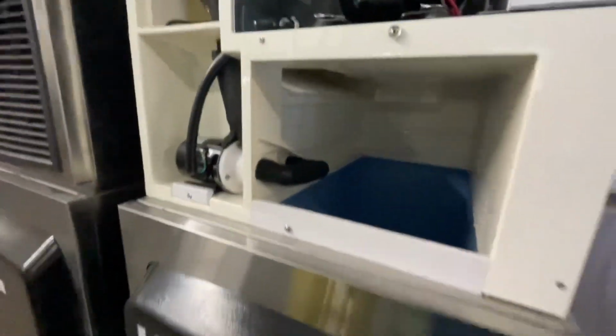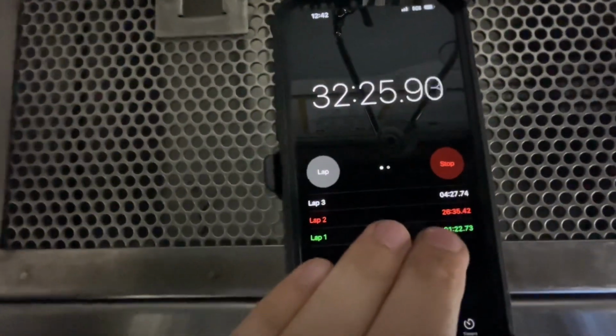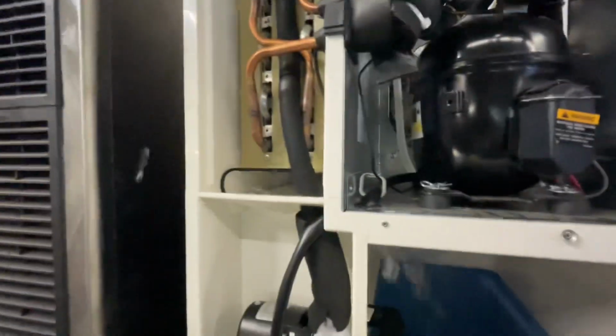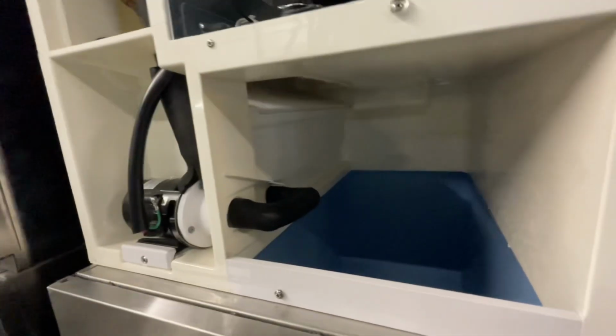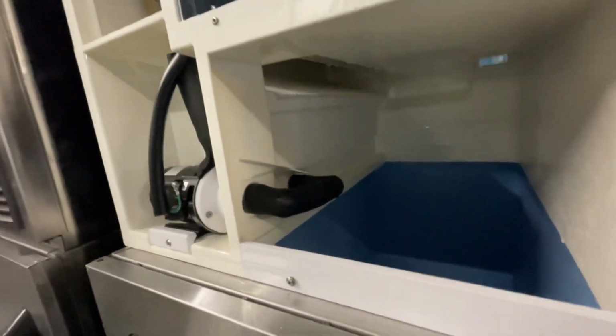So over 4 minutes into our harvest, let's see if we can get a good shot of what's going on over there. You still see ice cubes all over that evaporator. They should be mostly gone by this point. That's a 26-minute freeze, 4.5 minutes into harvest. Still have, there's a good shot, but more than likely it experienced a freeze up.